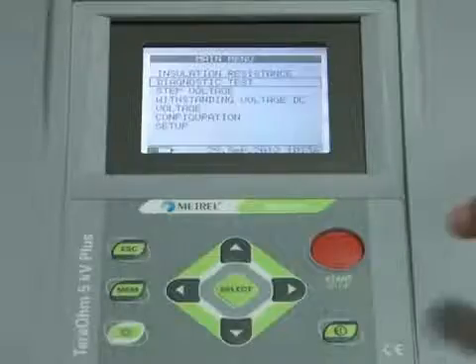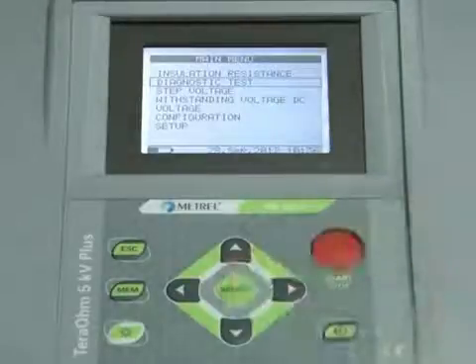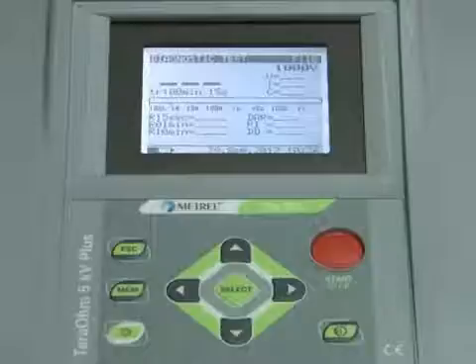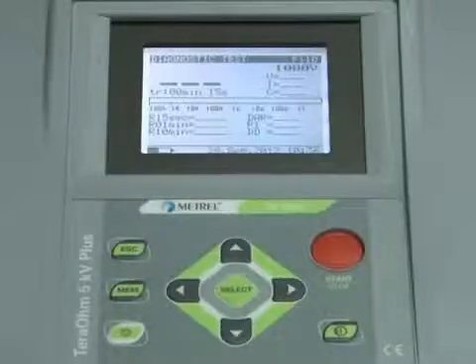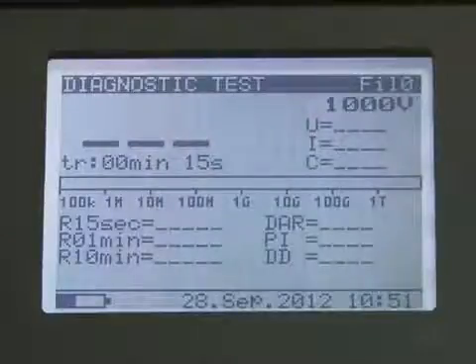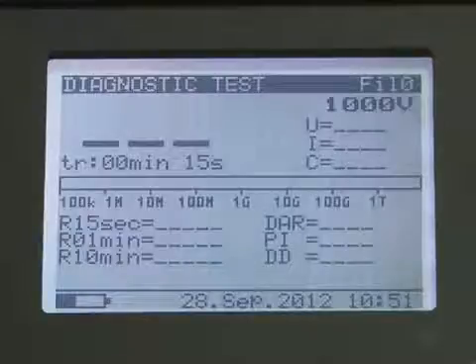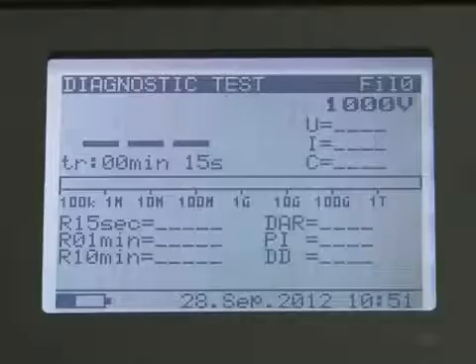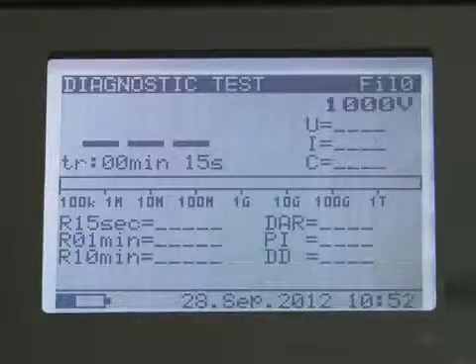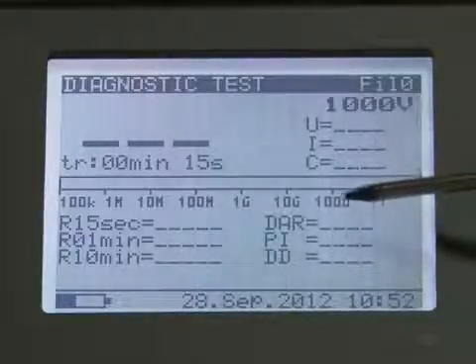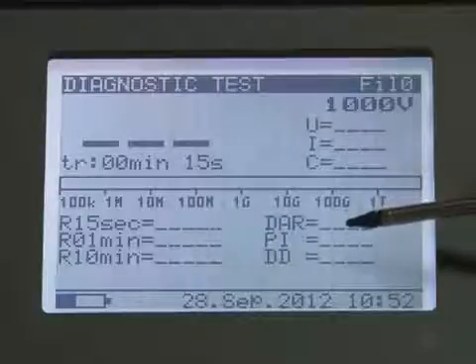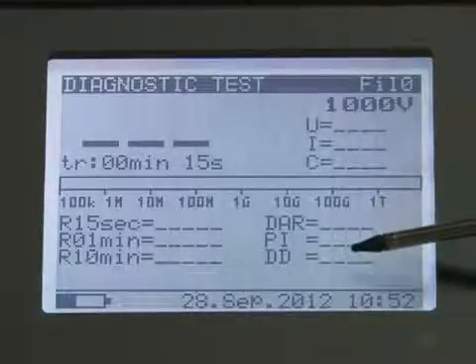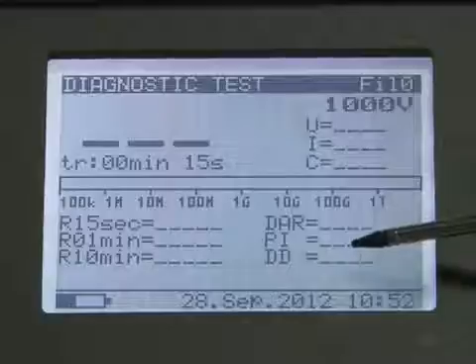The diagnostic test is a long-duration test for evaluating the quality of insulation material under test. The results of this test enable a decision to be made on the preventive replacement of insulation material. The Mi3201 displays dielectric absorption ratio, polarization index, and dielectric discharge testing.